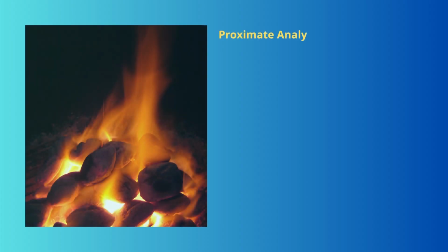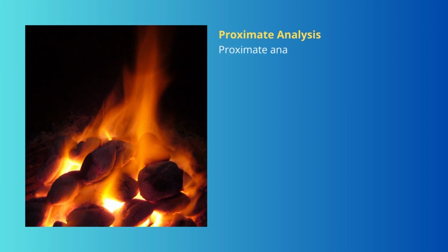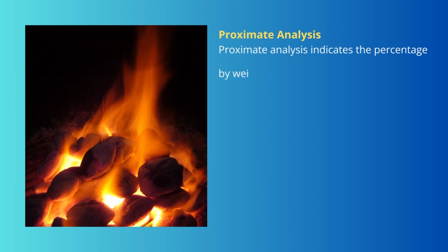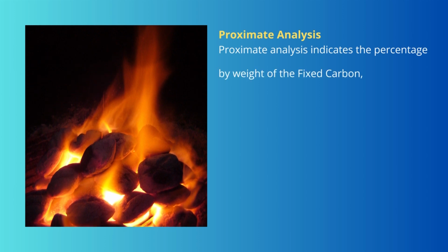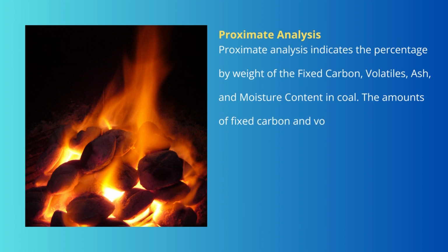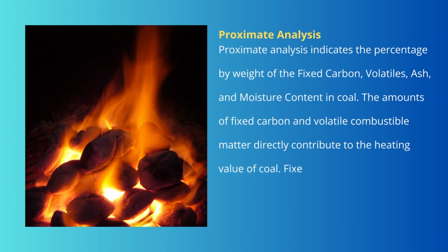Now, you people might have a question in your mind: what is proximate analysis? Let us deal with proximate analysis. Proximate analysis indicates the percentage by weight of the fixed carbon, volatiles, ash and moisture content in the coal. The amounts of fixed carbon and volatile combustible matter directly contribute to the heating value of the coal. Fixed carbon acts as a main heat generator during burning.